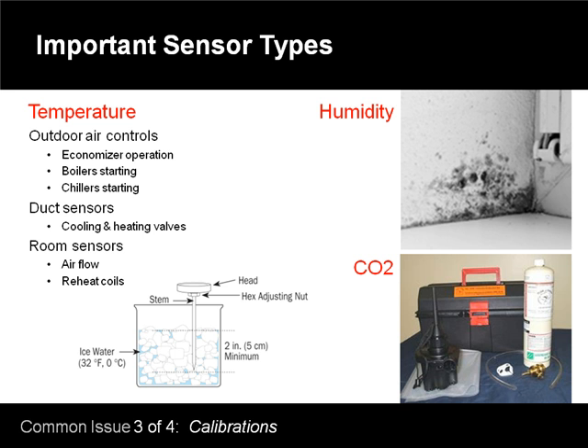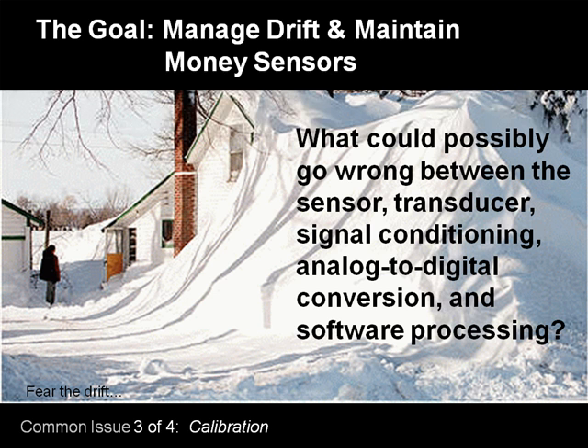You also have sensors, usually temperature or humidity sensors, put in ductwork. They're operating a cooling valve or a heating valve. They could be operating a steam humidifier. They could be operating a reheat coil, so you're running your heating and then opening up your cooling at the same time to try to counteract it. Room sensors, as we talked about, run your reheats, and they determine how much airflow is going to go into your space. When you are running too high of airflow, you have a fan back there that's ramping up high to overcome your deficiency.